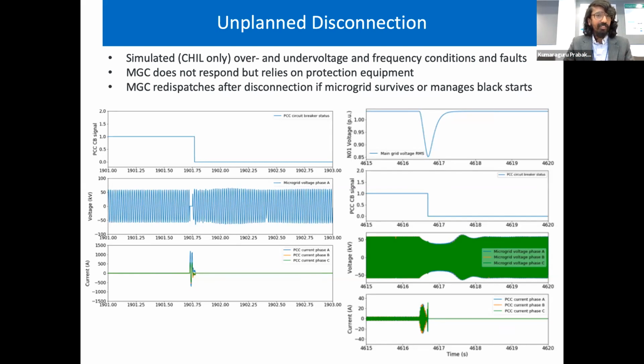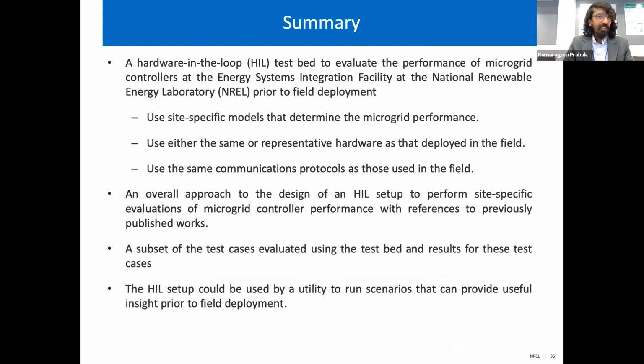In summary, we built this hardware-in-the-loop setup, which is very useful for evaluating microgrid controller functions, inverter functions, and energy storage functions before installation in the field. This helps de-risk investments before they go into the field. We identified a lot of bugs that could have caused issues in the field, captured them, and gave feedback so they could be updated before deployment. On the RTDS and digital real-time simulator side, we use models very close to reality, so this is probably the closest way to evaluate these things before installation.